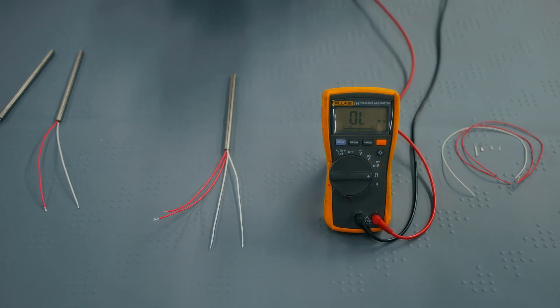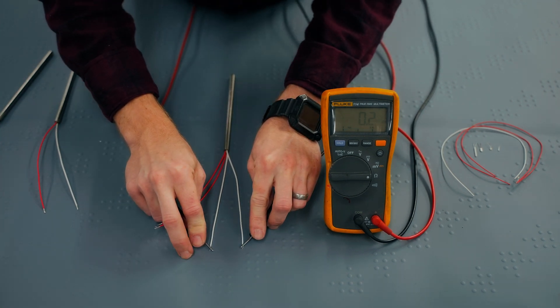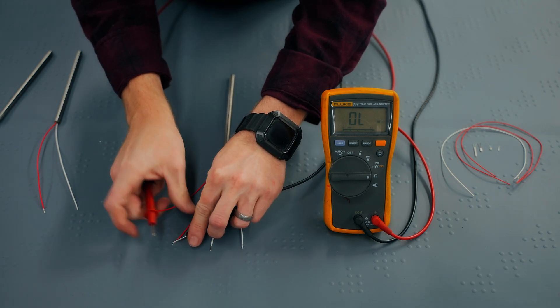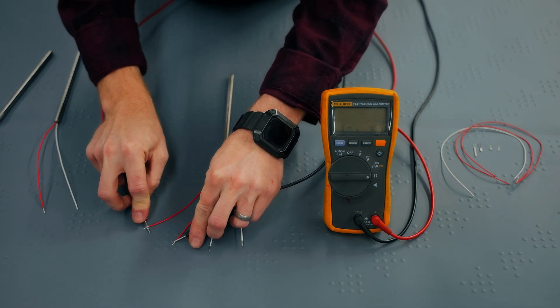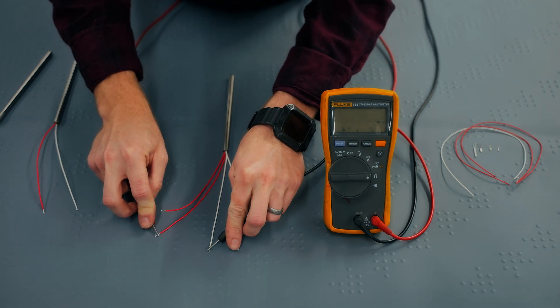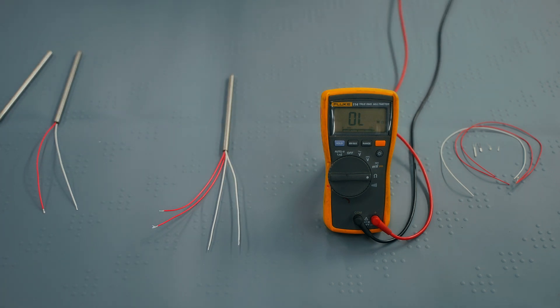On a four-wire RTD, the wires are connected in pairs. Two go to one side of the element, and two go on the other side of the platinum element. Check the resistance between both pairs of like color wires, and make sure it reads close to zero ohms. Then, check the resistance between any two dissimilar color wires. This RTD also reads about 109 ohms, so it's functional.